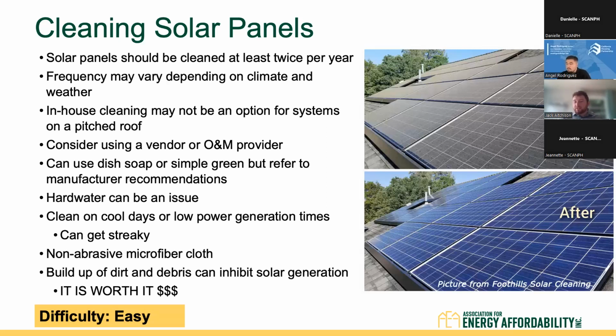That's best practice, not required. On cool days, if the water dries too fast, it can get streaky. If you're cleaning during a time of high power generation, you're going to get less power generation because you're cleaning. However, you should just do it. It saves you a ton of money, and it significantly improves the kilowatt hour generation of solar PV systems. And then use a non-abrasive microfiber cloth. You don't want to scratch the glass. Buildup of dirt and debris can inhibit solar generation, so it is worth it to do.